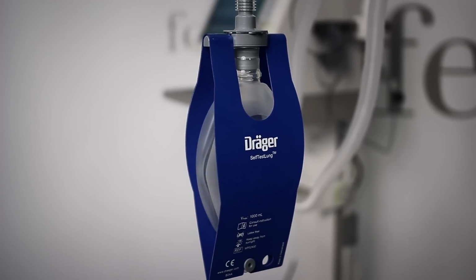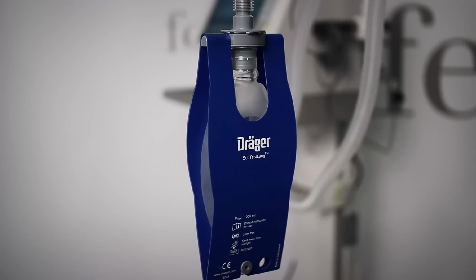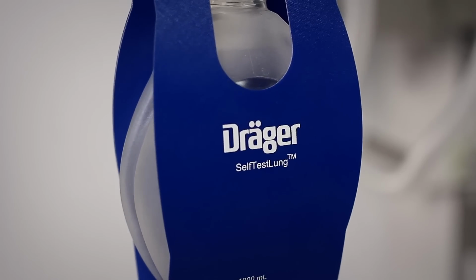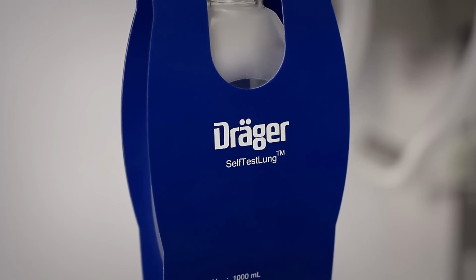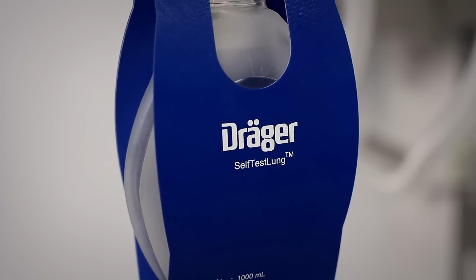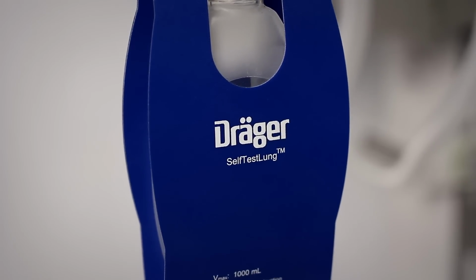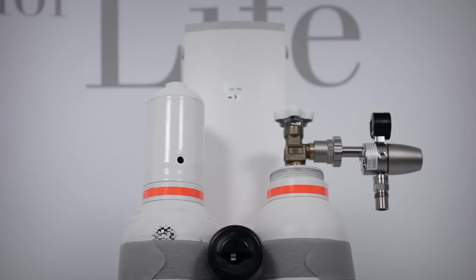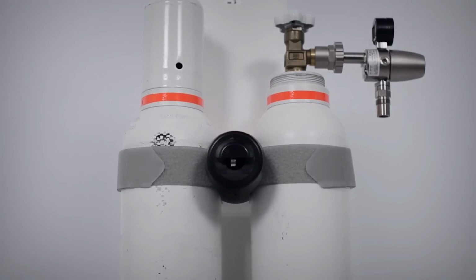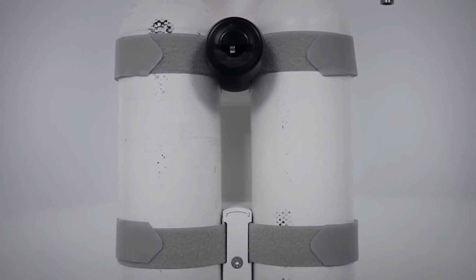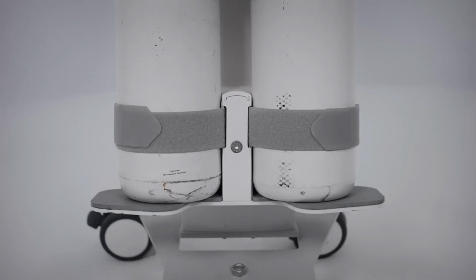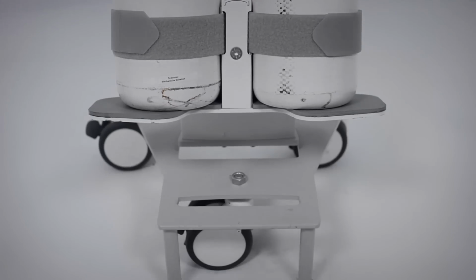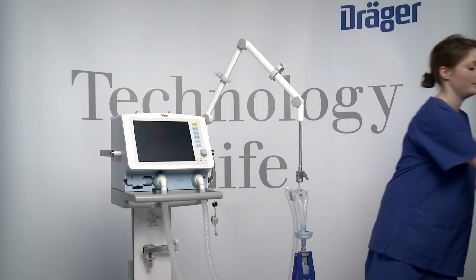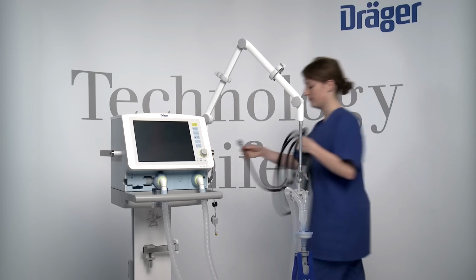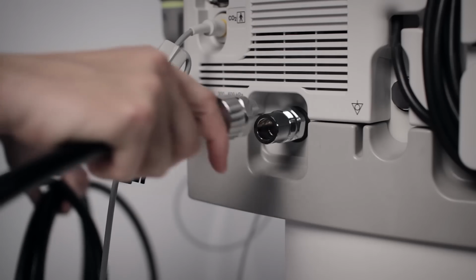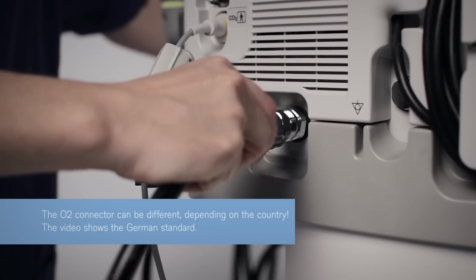In the high-pressure oxygen mode, HPO, O2 supply is provided by a central gas supply system or by compressed gas cylinders. In the low-pressure oxygen mode, O2 supply is provided by an external low-pressure oxygen source, for example O2 concentrator. For supplying from compressed gas cylinders, Savina 300 can be equipped with a transport supply unit or a cylinder holder. For O2 supply from a central gas supply system, connect the O2 compressed gas hose with the O2 connection of Savina 300.